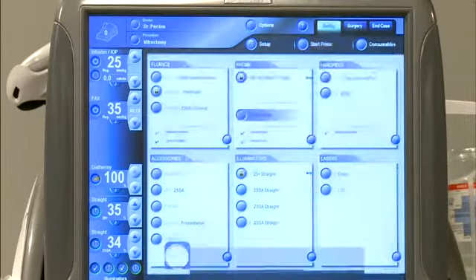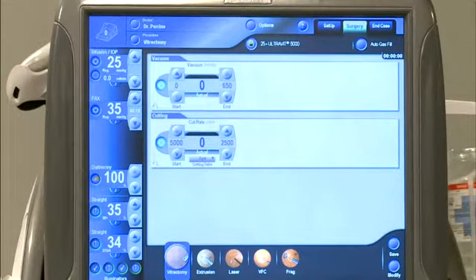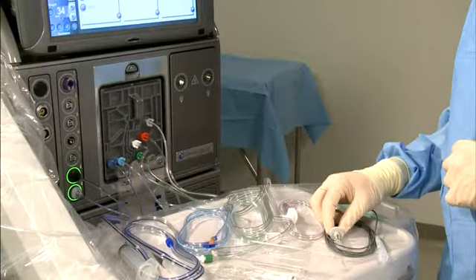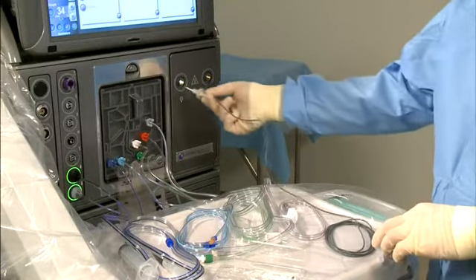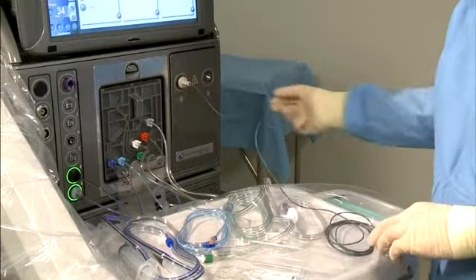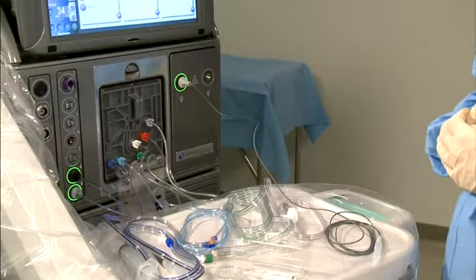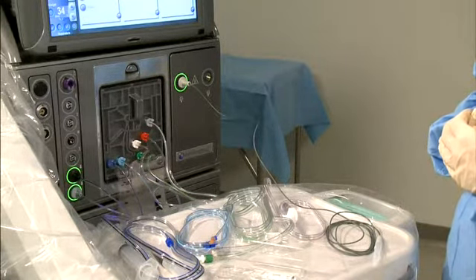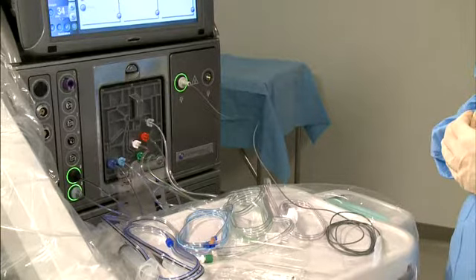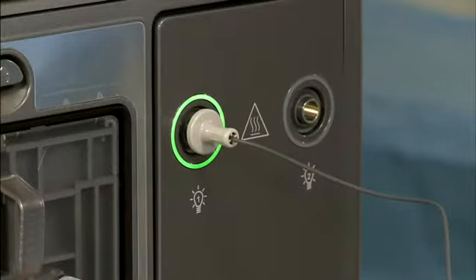After priming and tuning is complete, the system will automatically proceed to the surgery screen. The scrub nurse carefully uncoils the fiber-optic illuminator probe and inserts the connector into the illumination port. Always start at the default settings, then increase only when the surgeon requests. The RFID illumination ring will turn green, showing proper placement. For more detailed instructions, please consult the operator's manual or the directions for use.